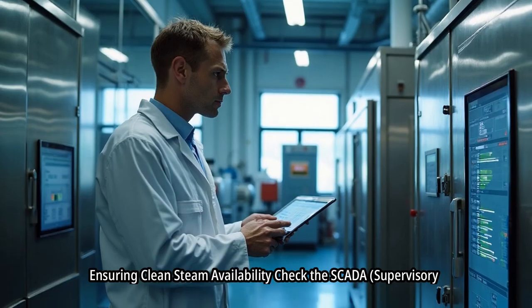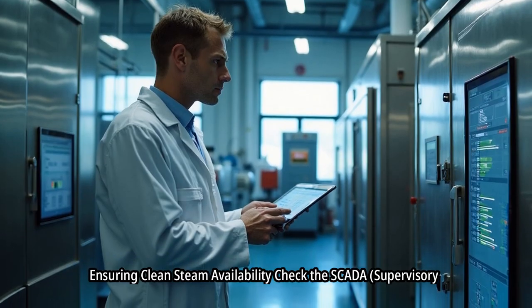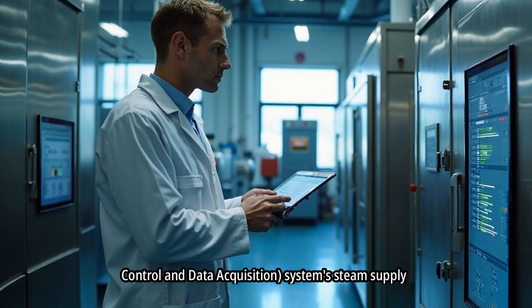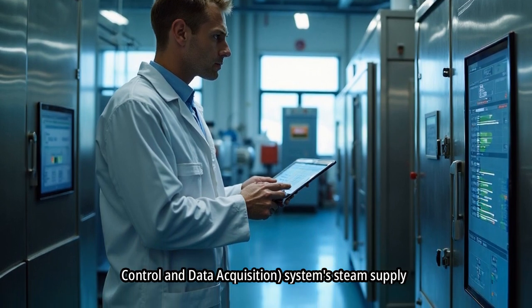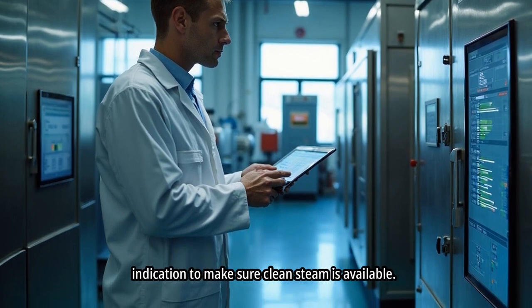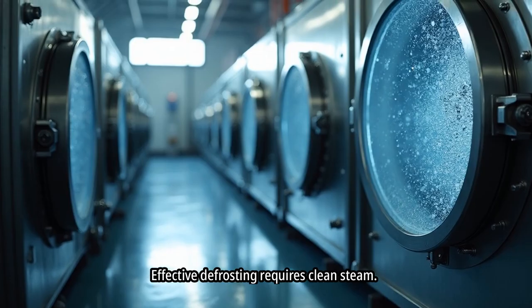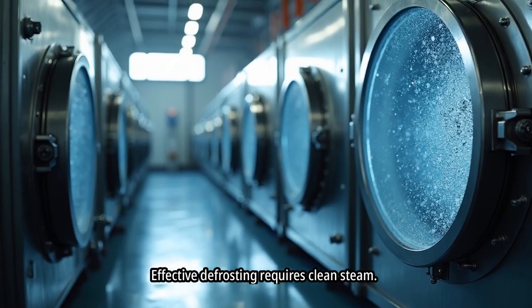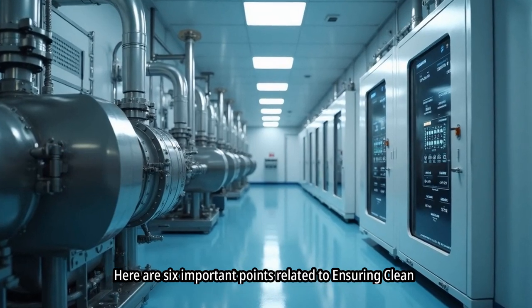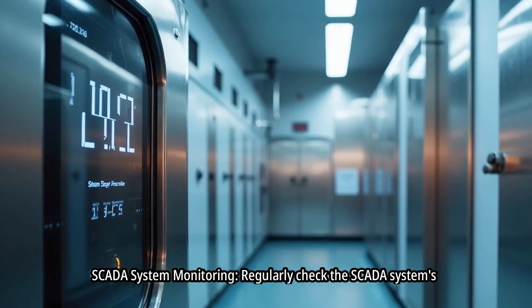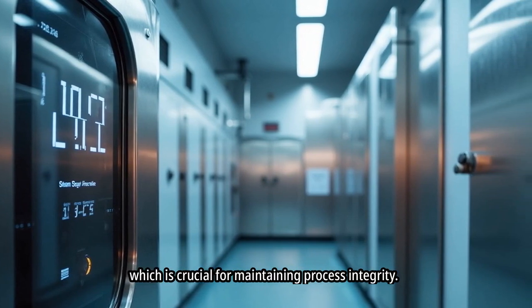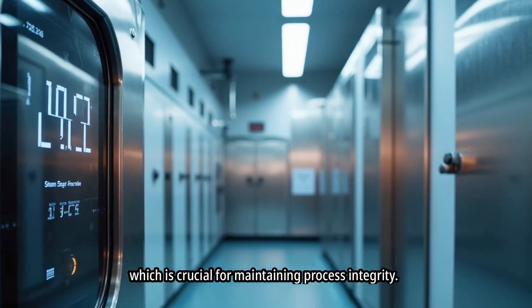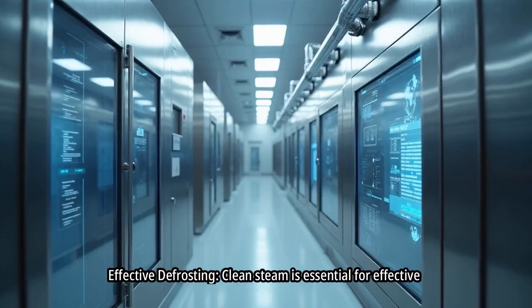Ensuring clean steam availability: check the SCADA, supervisory control and data acquisition, system steam supply indication to make sure clean steam is available. Effective defrosting requires clean steam. Here are 6 important points related to ensuring clean steam availability. SCADA system monitoring. Regularly check the SCADA system's steam supply indication to ensure clean steam is available, which is crucial for maintaining process integrity. Effective defrosting.